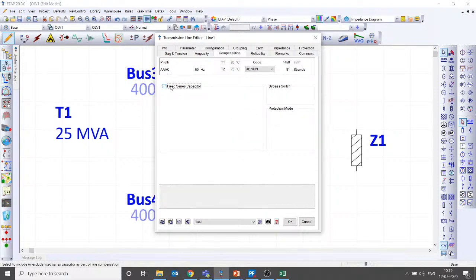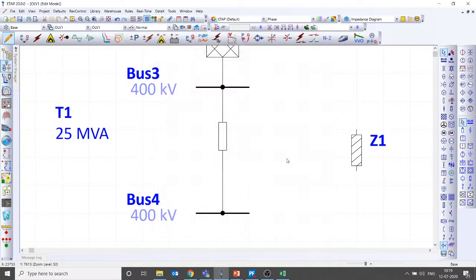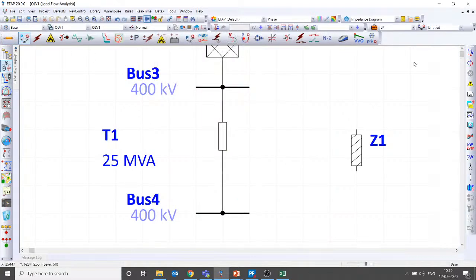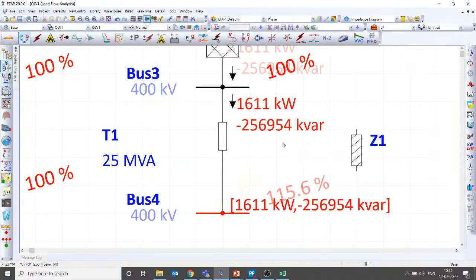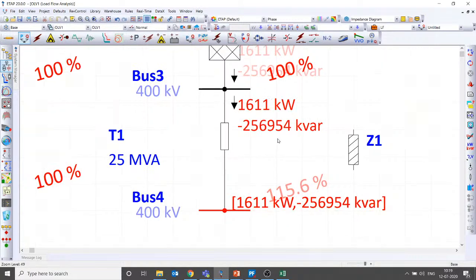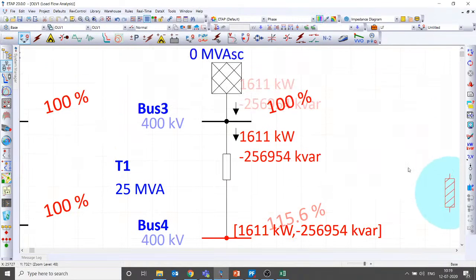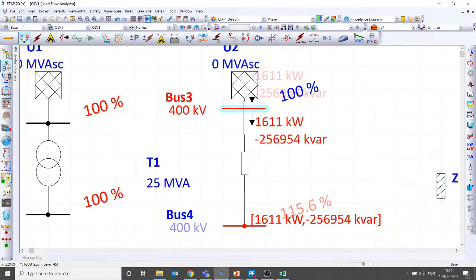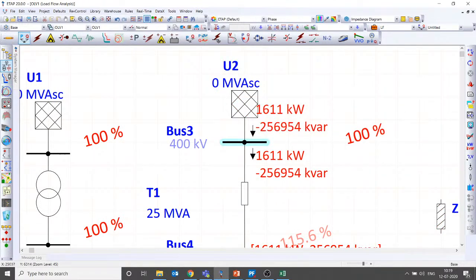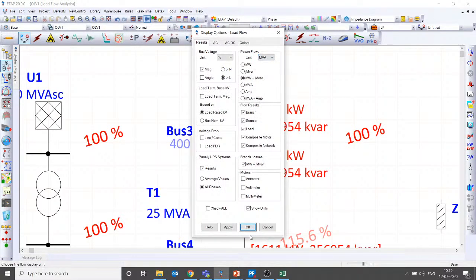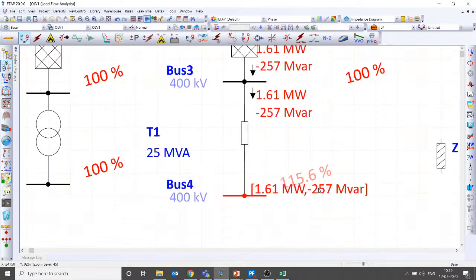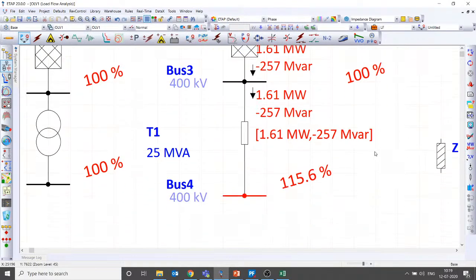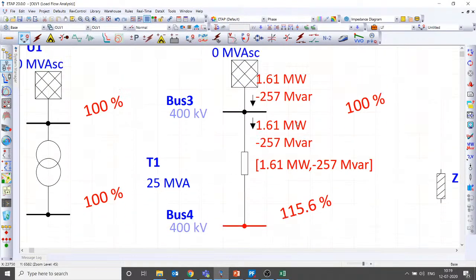So now let's assume there is no fixed series compensation. Let's assume some 400 kV 300 kilometer line. Let's try to plot the results. What's the loss which we are getting in the line? So let me slightly reduce the zoom so that you can understand these parameters. Yes, let me plot the results in megawatt so that it will be easy. Yes, so here you can see line length is about 300 kilometer. The loss is approximately about 1.6 megawatt, and reactive power is 257 Mvar.